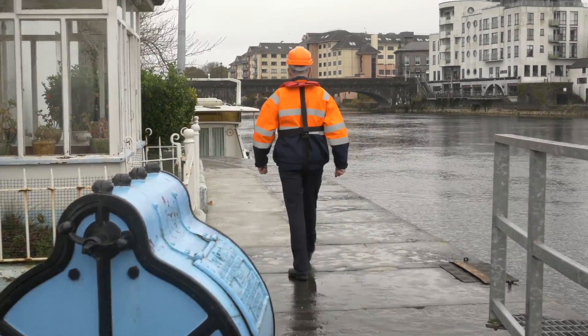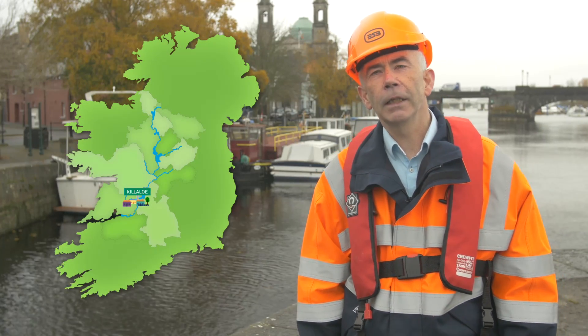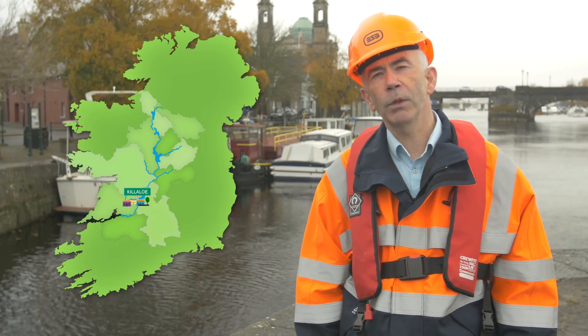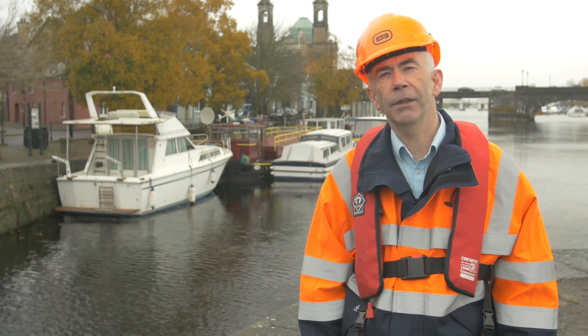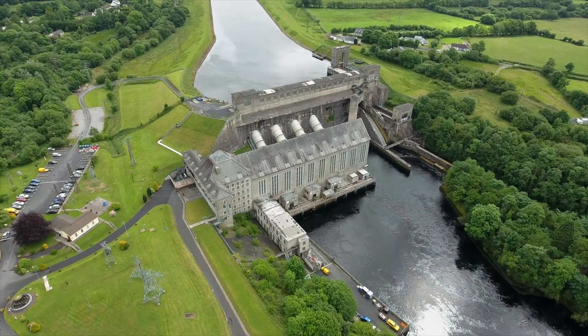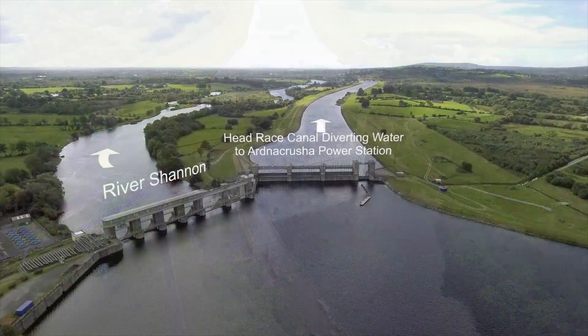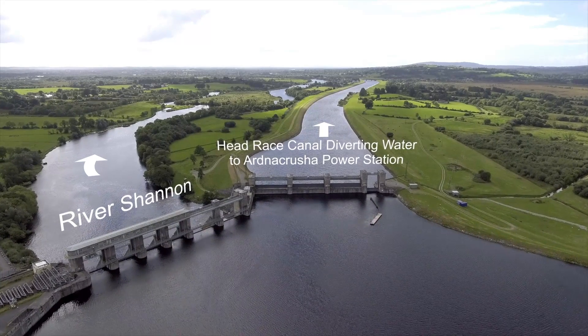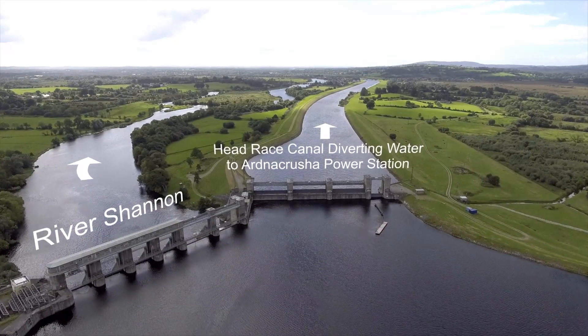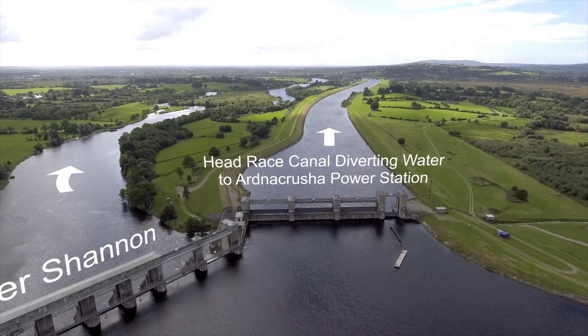ESB's role on the Shannon is to ensure the generation of electricity at Ardnacrusha. South of Lough Derg and Killaloe, the gradient on the river, which has been relatively flat up to that point, becomes steeper. Between there and Limerick City, there's a 30-metre drop in level, and it is the energy in the water associated with this drop in level that the builders of Ardnacrusha harnessed when they built the scheme in the 1920s. In order to harness the water energy, they had to divert water away from the Shannon, which was achieved by building a 12-kilometre man-made canal to the power station at Ardnacrusha.